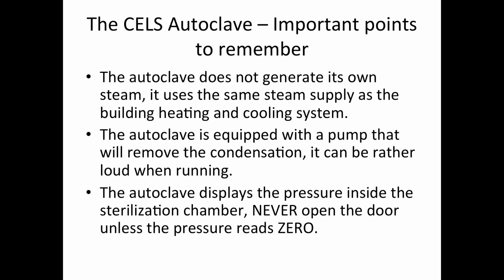Firstly, the autoclave does not generate its own steam, and it uses the same steam that the building uses for heating and cooling, which means, of course, that we are dependent on the steam supply from the campus cogeneration plant. So there may be interruptions, there may be fluctuations in pressure, and amines are added to the steam for pH control. So there might be a chemical reaction with that steam, with those amines, and a sample. The autoclave is equipped with a pump that will remove any condensation, and it can be rather loud when it is running. And the autoclave is set up to display the sterilization temperature and the pressure inside the sterilization chamber. You never want to open the door unless the pressure inside is reading 0 or the system software gives you a "it's safe to open the door" message.